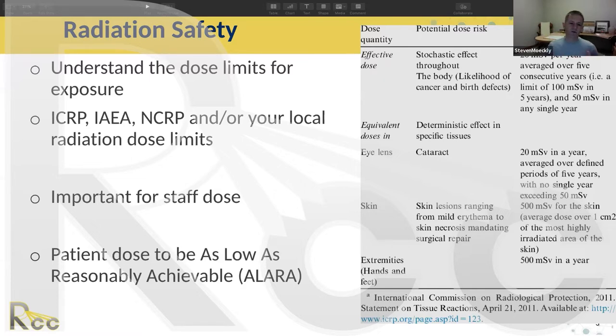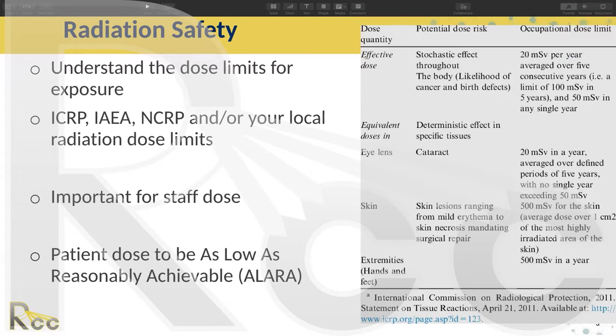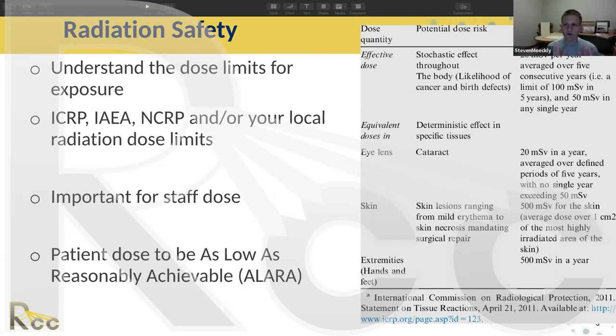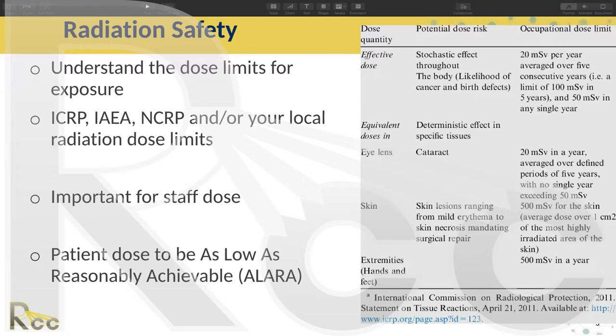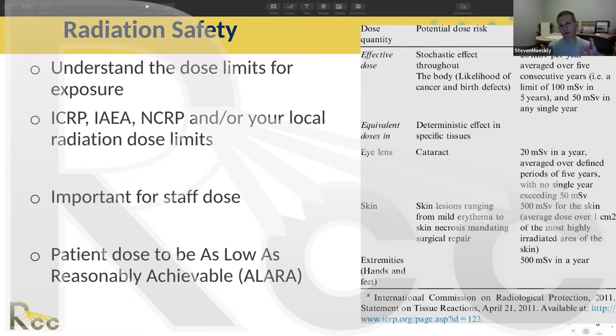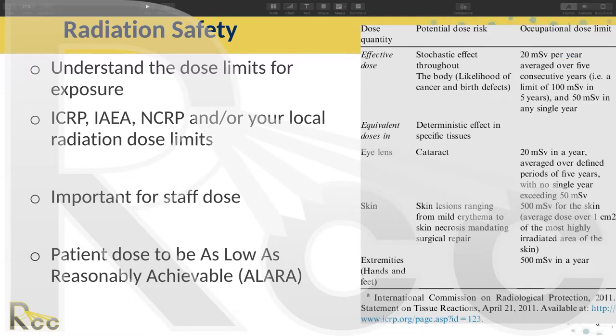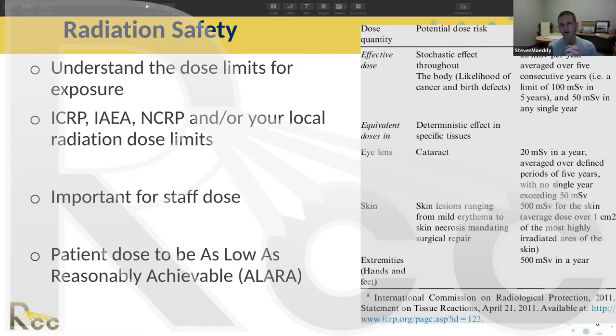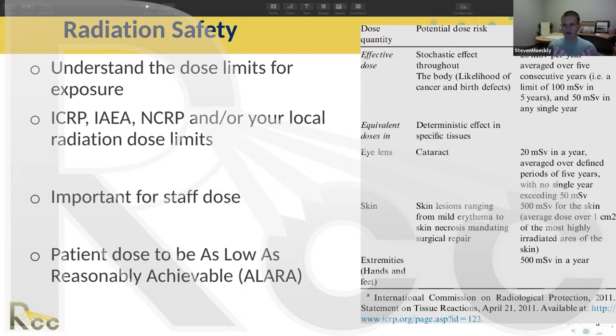One thing to think about in designing a vault: you don't have to have staff doses be zero. You need to know your regulatory limits. For instance, we have a vault where during treatment I have a meter out actively reading radiation — it's shielded much like a PET vault. We do get a little bit of dose, but it's in the millirem region. That can save you some money if you're looking at the cost of shielding.